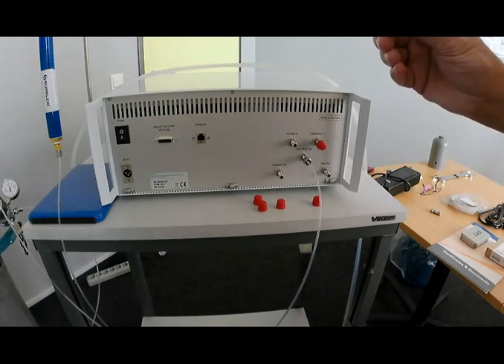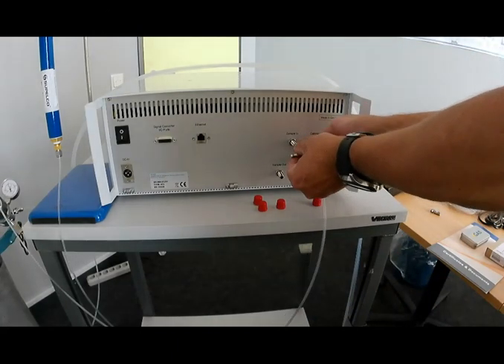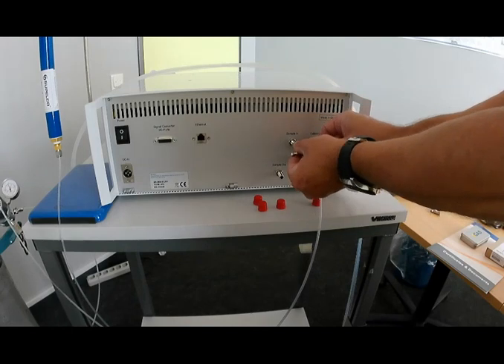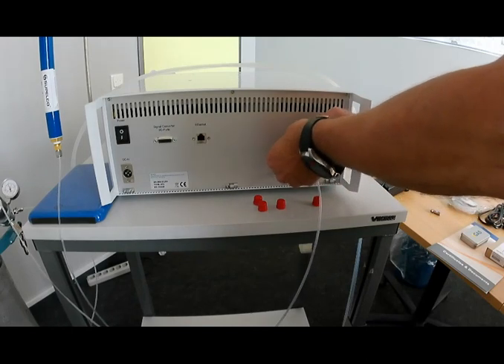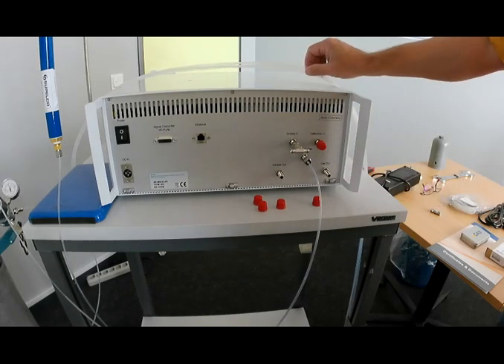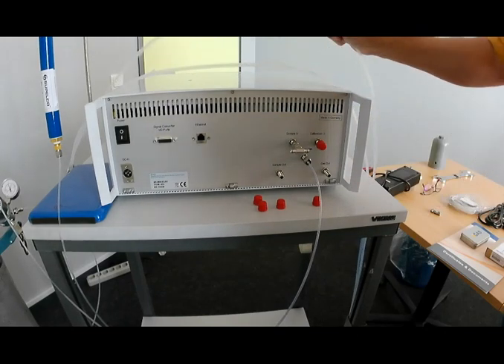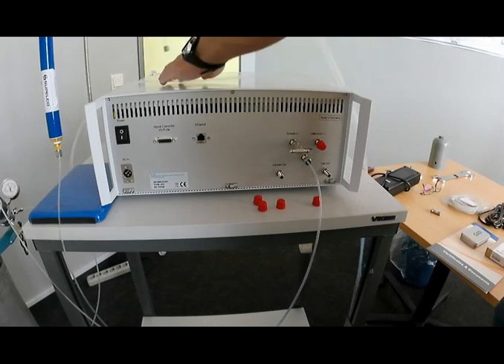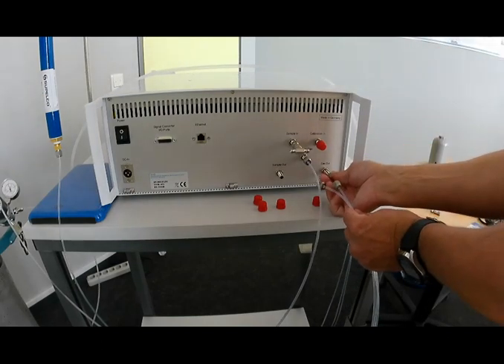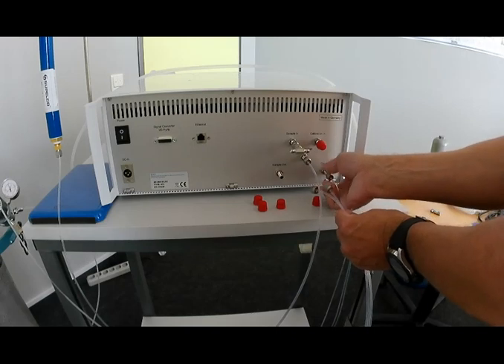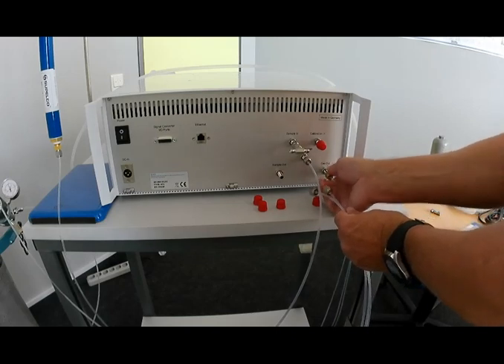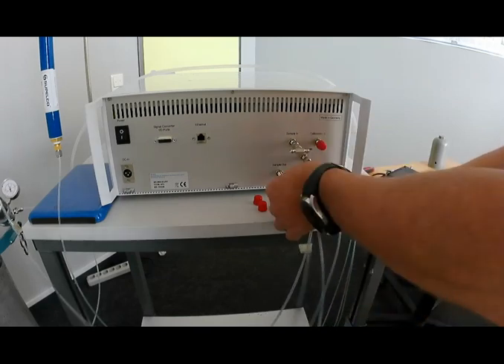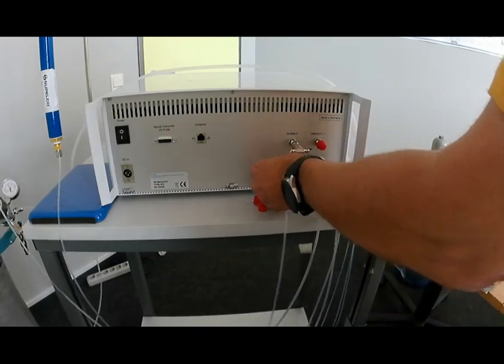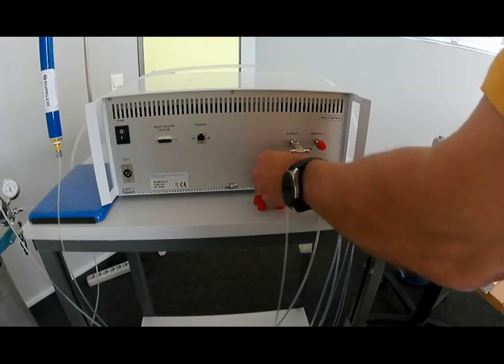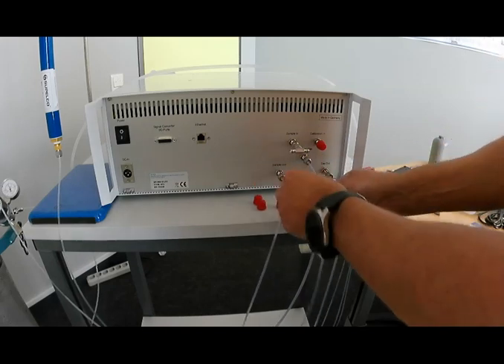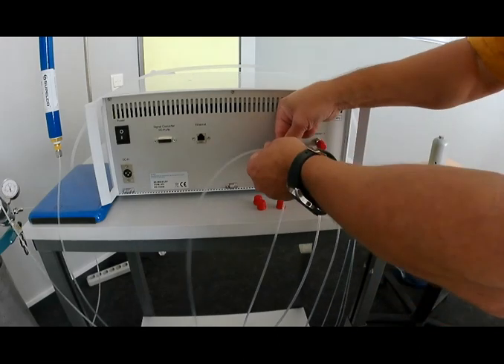For continuous measurements, we recommend a bypass configuration. Remember that the bypass flow has to be at least 200 milliliters. We attach an outlet to the bypass and also outlets to gas out and sample out. These 3 outlets should not have a vacuum sucking on it. They have to be guided into a ventilation hood.